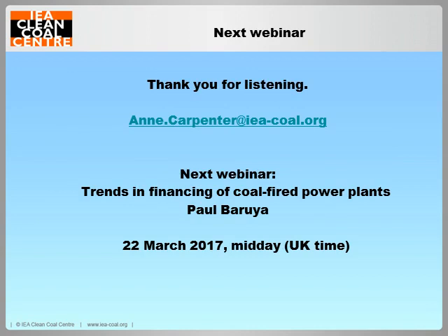And it seems like we have one more question. So it reads, do FGD processes have any effect on CO2 emission and hence water consumption? Yes, with flue gas processes, if you've got a reagent such as limestone or sodium carbonate, then as they react with the SO2, carbon dioxide is formed as a byproduct. So CO2 emissions will then increase if they're not captured.